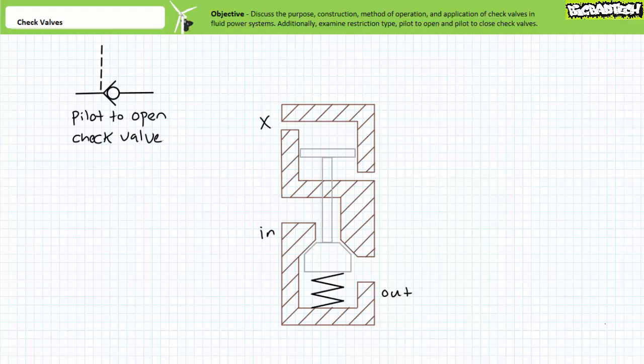Let me briefly introduce two more types of check valves before we discuss some basic check valve applications. The previously discussed check valves were direct acting in that fluid directly acts on the poppet face. Consider, however, a pilot to open check valve that in addition to direct action on the poppet receives a pilot pressure signal X from somewhere else in the system.